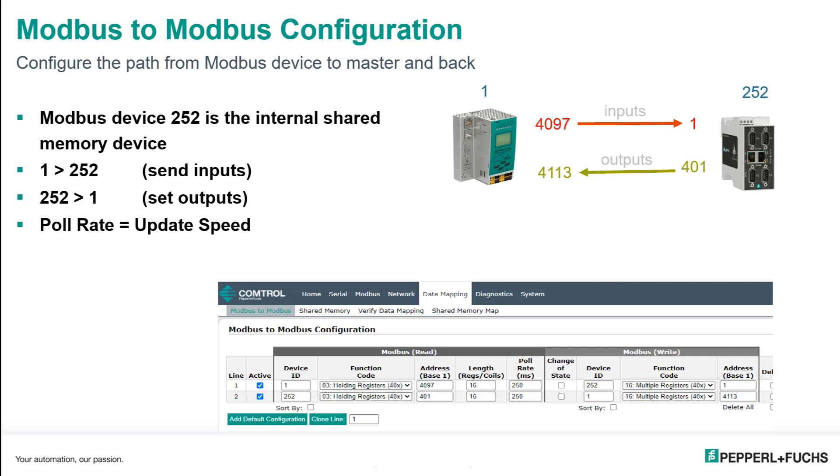Outputs are sent from the address 401. This is the internal memory of DeviceID252 to address 4113 of DeviceID1. And then lastly, adjust the poll rate. You want to adjust this so you get the inputs and outputs exchanged as quickly as you need it for your application.